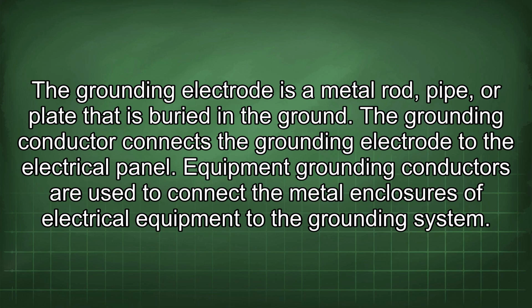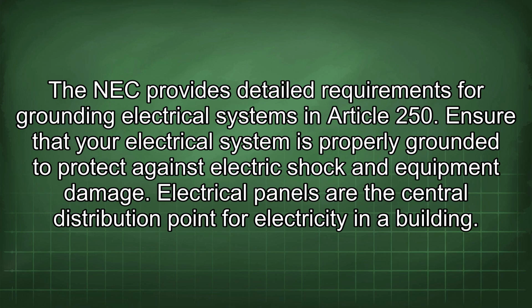The grounding conductor connects the grounding electrode to the electrical panel. Equipment grounding conductors are used to connect the metal enclosures of electrical equipment to the grounding system. The NEC provides detailed requirements for grounding electrical systems in Article 250. Ensure that your electrical system is properly grounded to protect against electric shock and equipment damage.